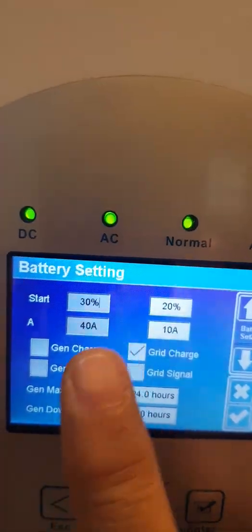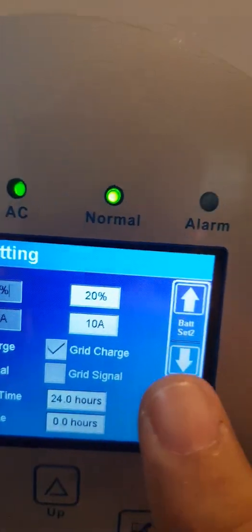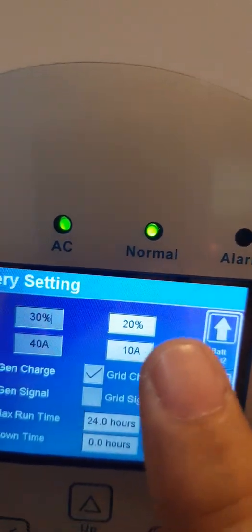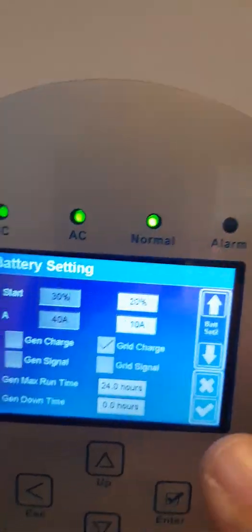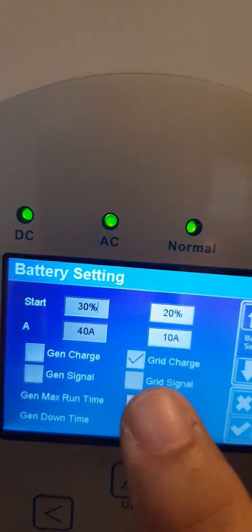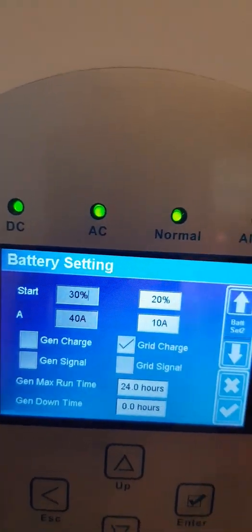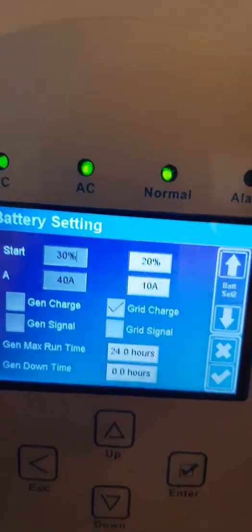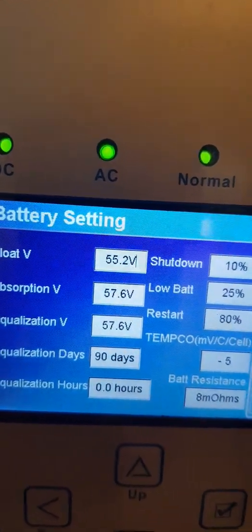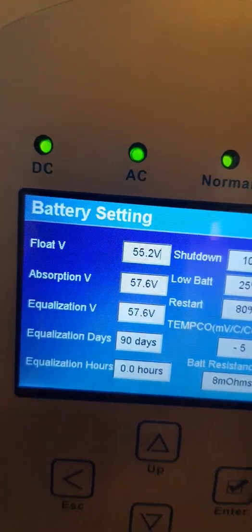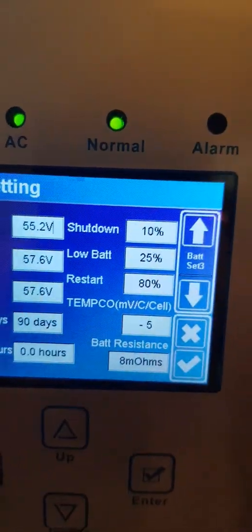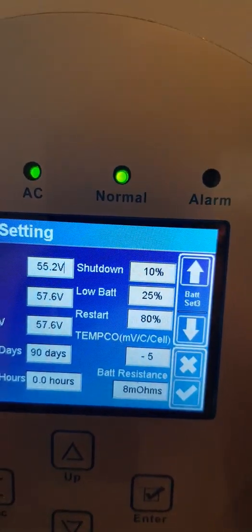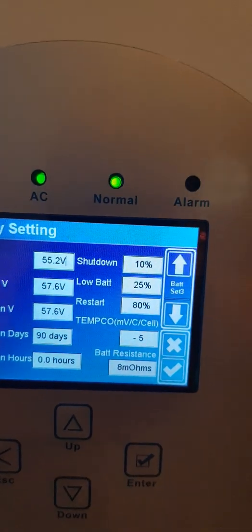We won't use this one because this is for generator. We set grid charge at 10 amperes, so we can do away with the charging if you are not using net meter. But if you have net metering, you can do grid charge in the morning or afternoon when there is sun. So next page. These are the specific voltages. Float is 55.2, 57.6 for the absorption. Equalization 57.6. Shutdown set at 10%. Low bat at 20, when it reaches around 25%, it will switch back to grid. So restart is 80%. So these are the only pages under battery settings.